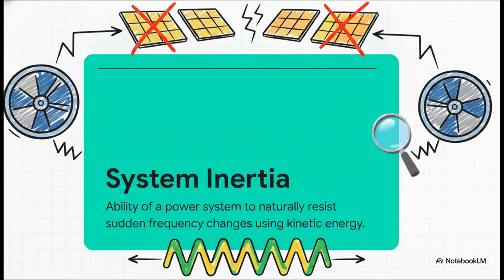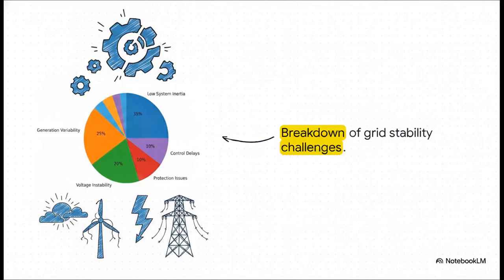Because system inertia is essentially the shock absorber for the entire grid. It's the ability of the power system to naturally resist sudden, dangerous changes in frequency, simply by leaning on the stored kinetic energy of those giant, spinning metal masses. When you swap out a spinning steel turbine for a static, silent solar panel, that vital shock absorber just vanishes. And the consequences of losing that shock absorber are pretty stark.